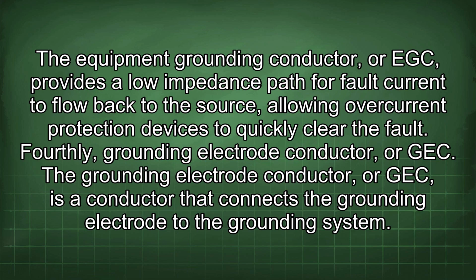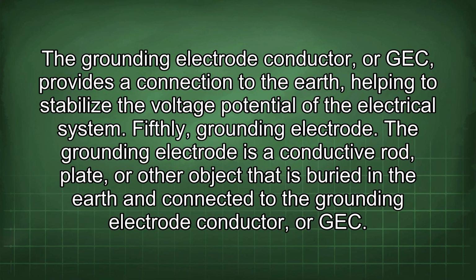Fourthly, grounding electrode conductor, or GEC. The grounding electrode conductor, or GEC, is a conductor that connects the grounding electrode to the grounding system. The grounding electrode conductor, or GEC, provides a connection to the earth, helping to stabilize the voltage potential of the electrical system.